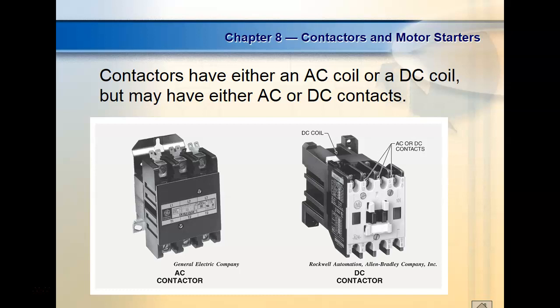DC is going to use a chunk of metal to concentrate the magnetic field. Because what's missing in DC? Relative motion. DC does no relative motion. So if I pick up two relays, one of them, the armature is a big old chunk of metal, the other one's laminated, I know right off the bat the laminated runs off with AC. And if it says 120 volts, that's 120 volts AC. If you put it across 120 volts DC, it's going to burn up because it doesn't get the AC reaction, right?